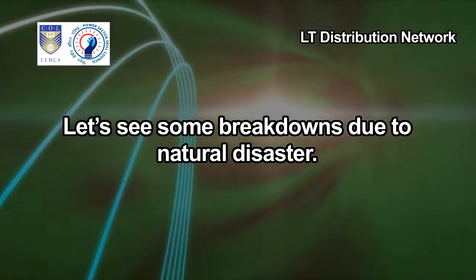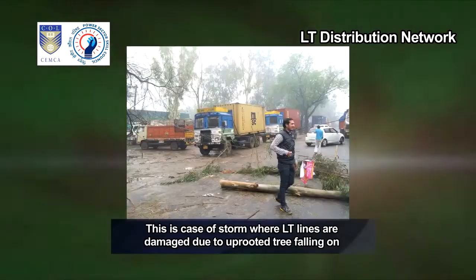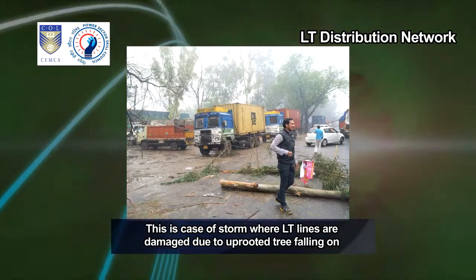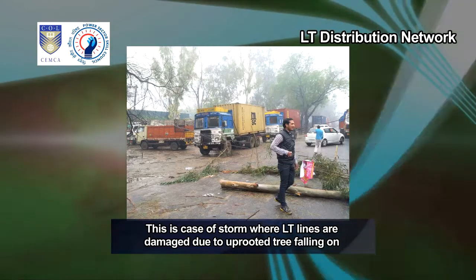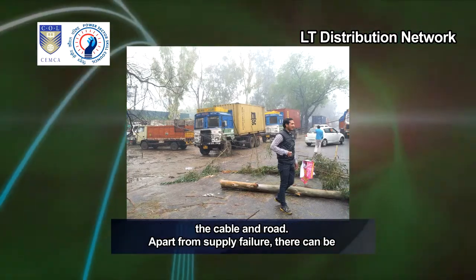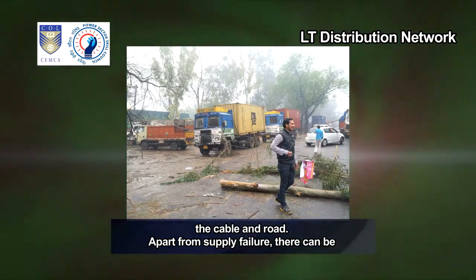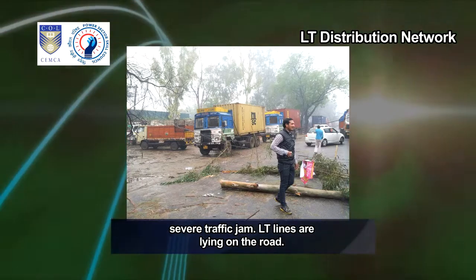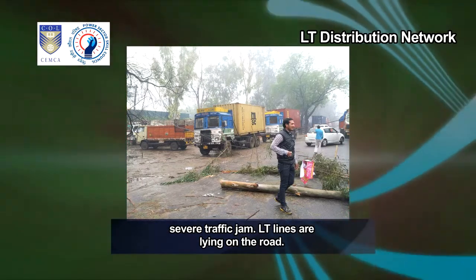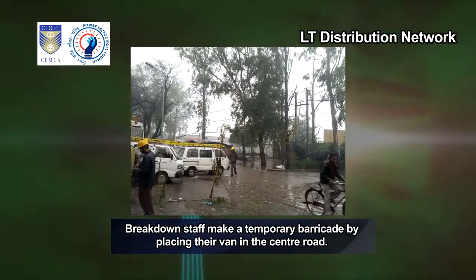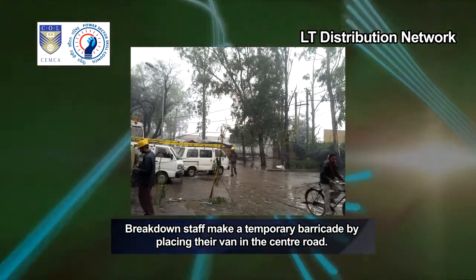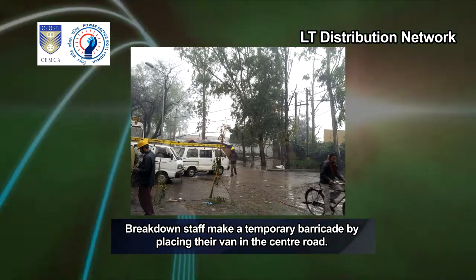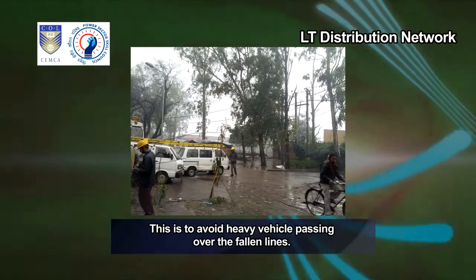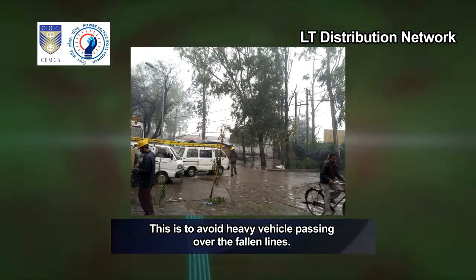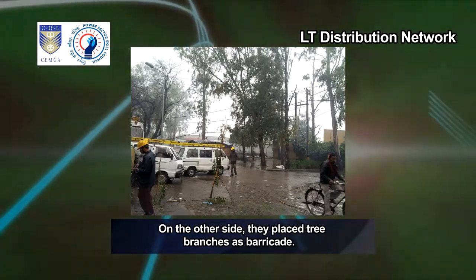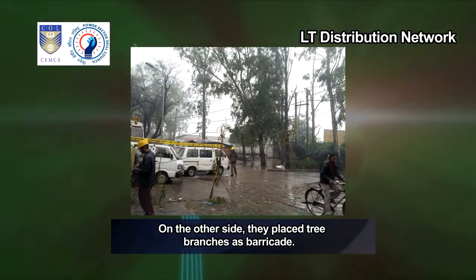Let's see some breakdowns due to natural disaster. This is a case of a storm where LT lines are damaged due to an uprooted tree falling on the cable and road. Apart from supply failure, there can be a severe traffic jam. LT lines are lying on the road. Breakdown staff make a temporary barricade by placing their van in the center of the road. This is to avoid heavy vehicles passing over the fallen lines. On the other side, they placed tree branches as a barricade.